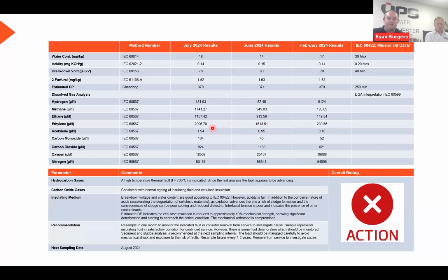So that's a really effective way for them to see that that high temperature thermal fault was active and allowed them to then take action over, which was indicated here in our fault, that it was a high thermal fault. And as you can see, if they'd just done fluid quality, the fluid itself, okay, the acidity was fair due to it being a category B, due to its size. But if they'd only done that, they wouldn't have picked up that there was an actual fault. The fluid was fine, but there was a fault.